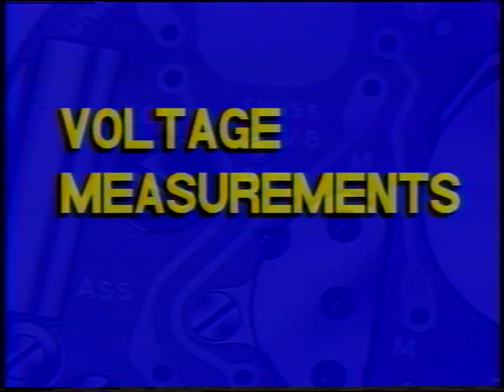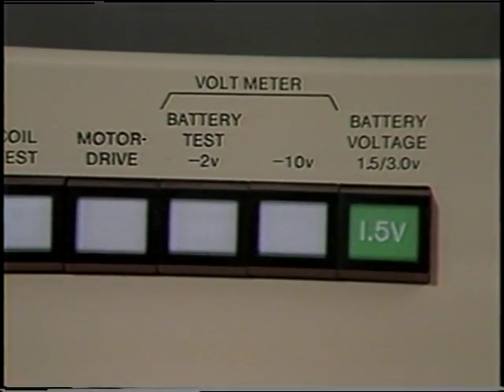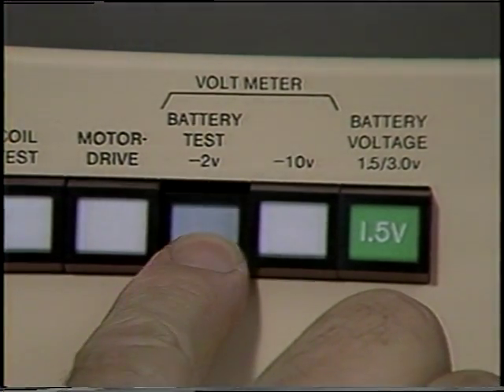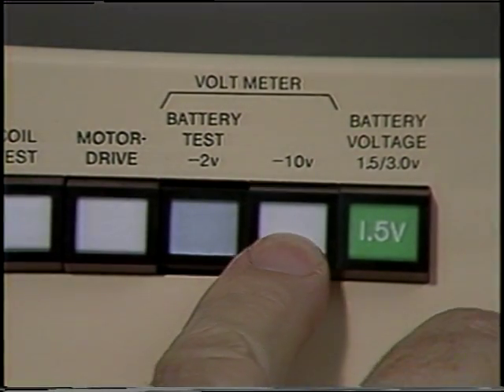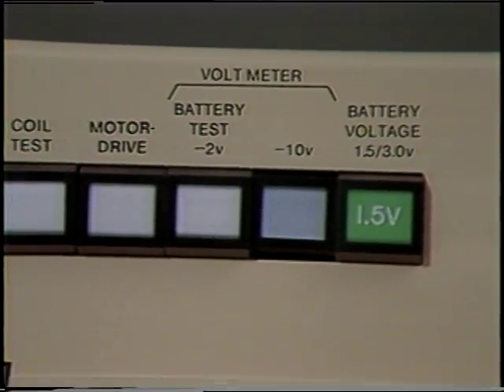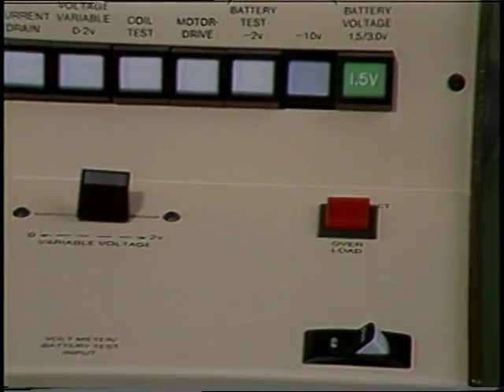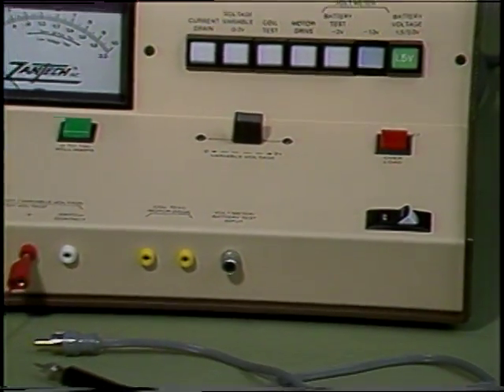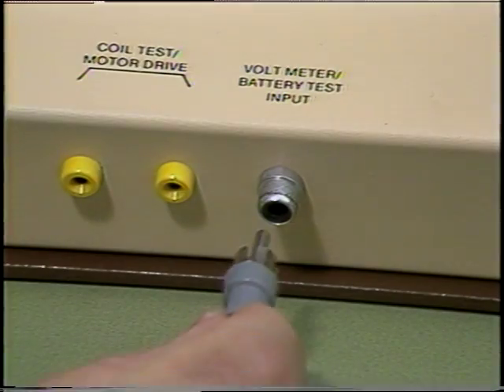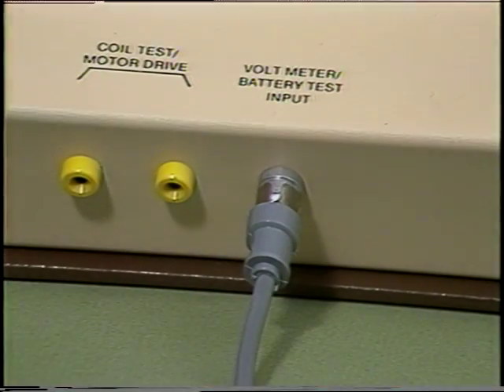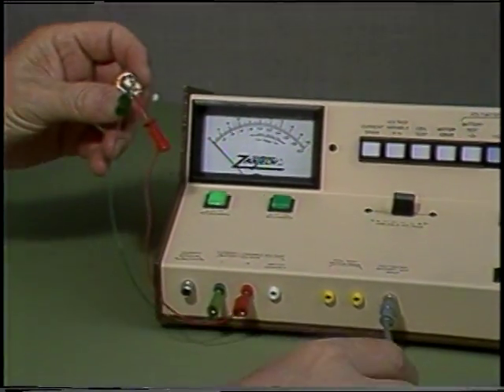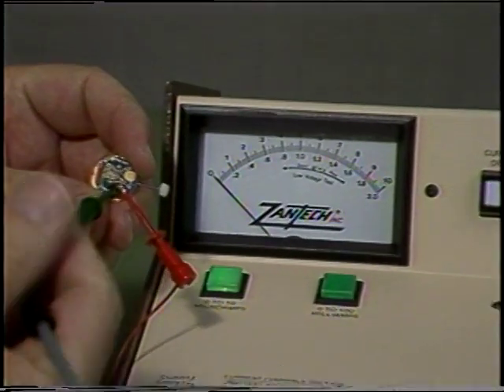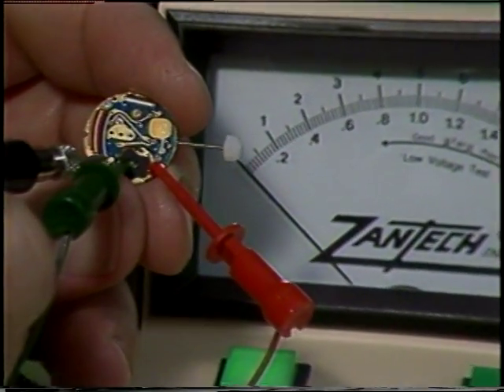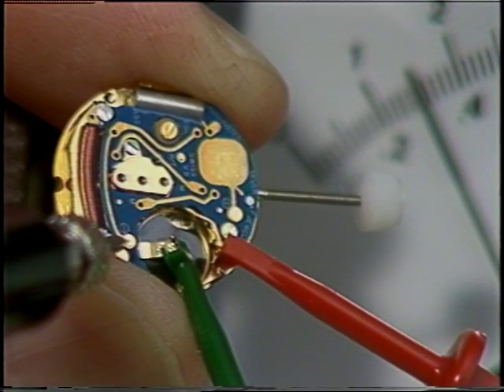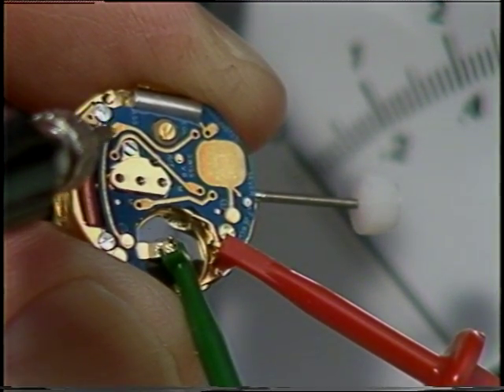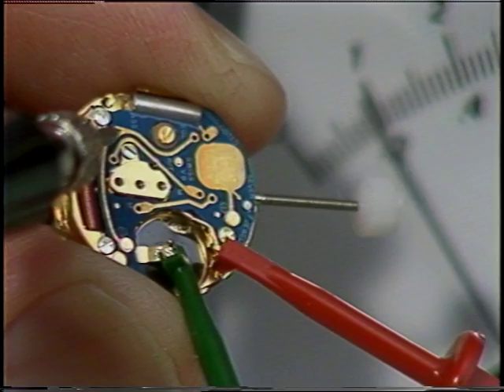Voltage measurements. There are two voltage measuring ranges, a 0 to 2 volt range and a 0 to 10 volt range. When either of these two buttons are pushed in, the meter becomes a very high impedance voltmeter. The voltmeter probe can then be used to measure voltages on any quartz watch without loading the circuit. When a module or movement is connected to the main power source through the battery terminals of the instrument, it is only necessary to use one shielded probe to measure voltages on the circuit board.